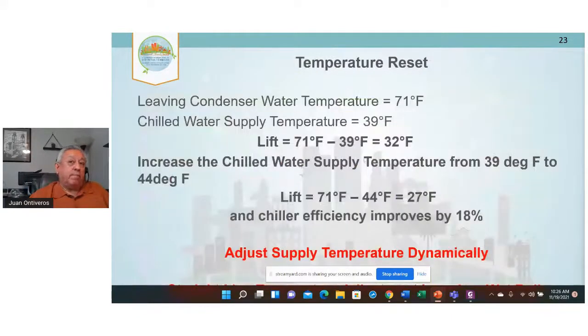So here's what happens. By also resetting temperature: condenser water temperature is 71, the chill water supply temperature is 39, degrees lift, 32. If I increase the supply from 39 to 44, lift improves 18%. So we also wanted to adjust the supply temperature. In the past, historically, we had always sent chill water at 39 degrees. But in the winter, you don't need 39 degrees. You can go warmer. And so we decided we wanted to adjust the supply temperature dynamically.